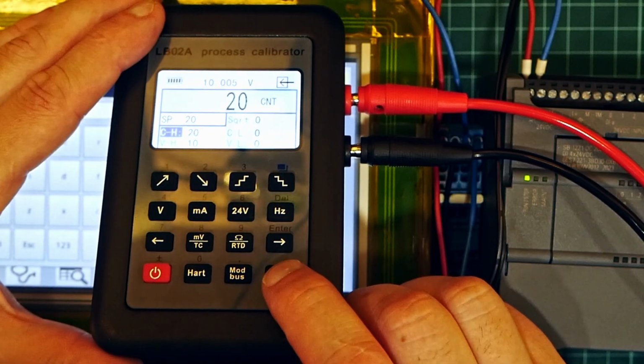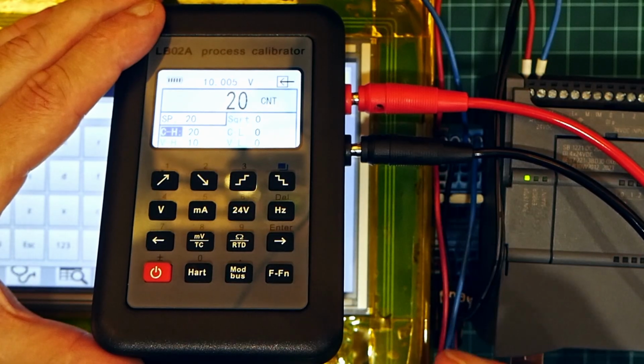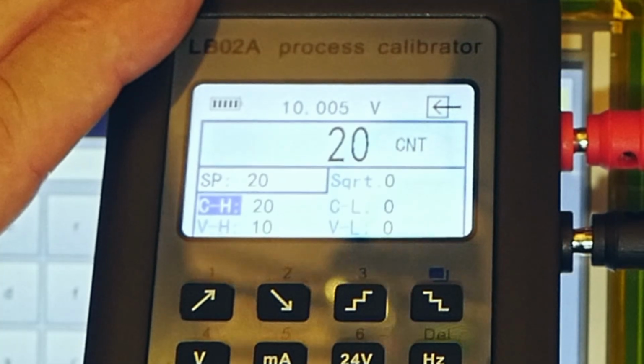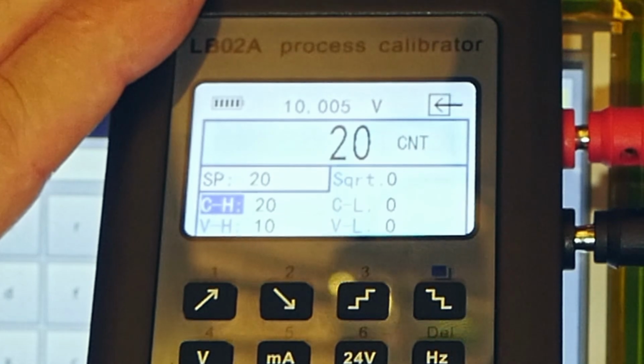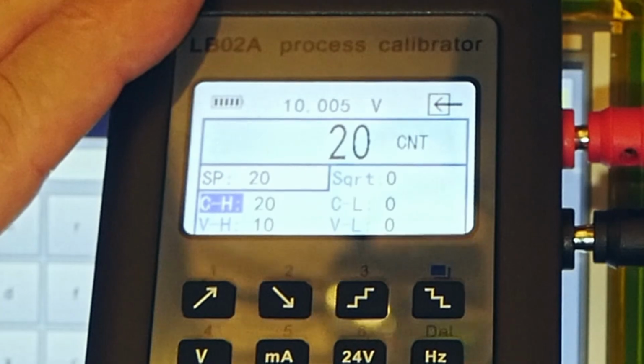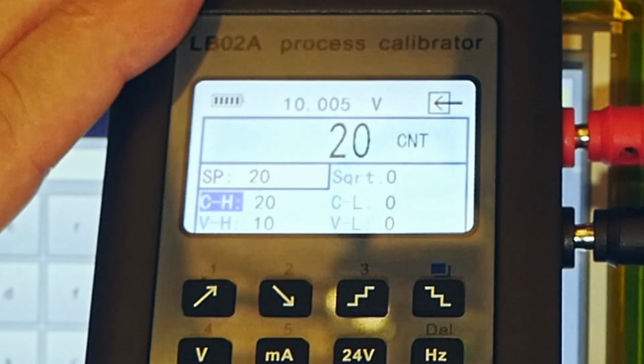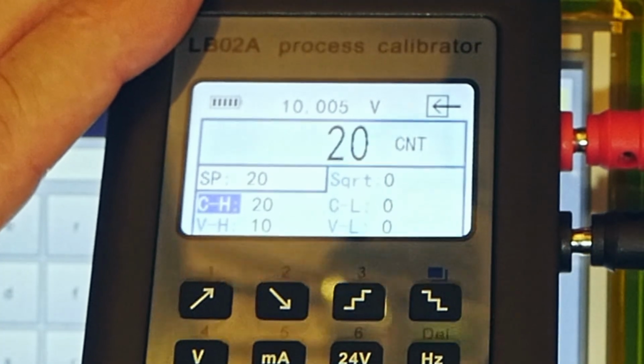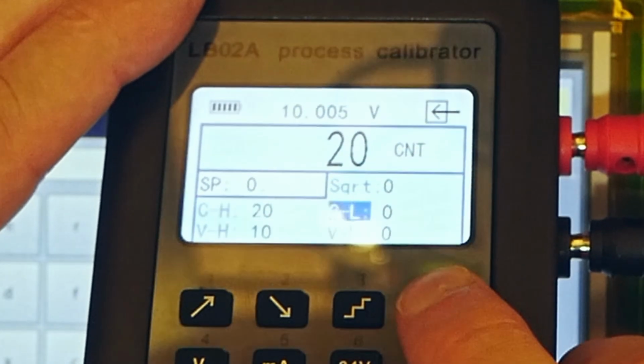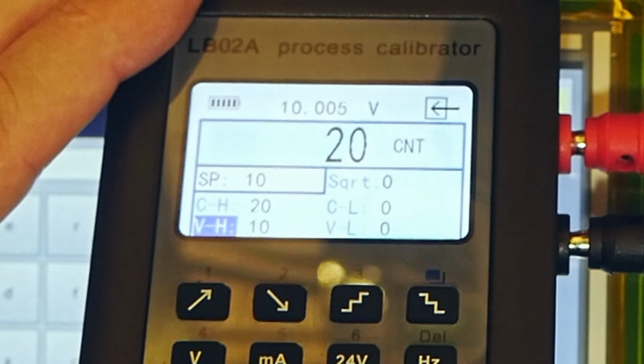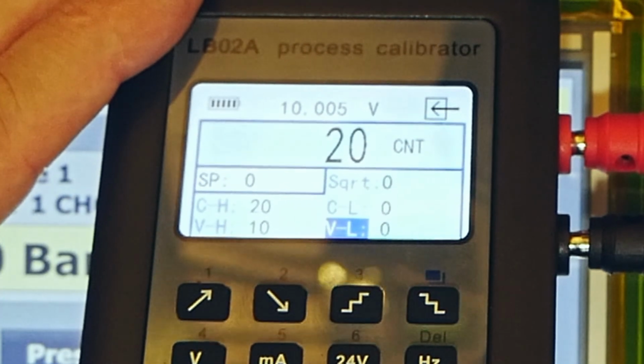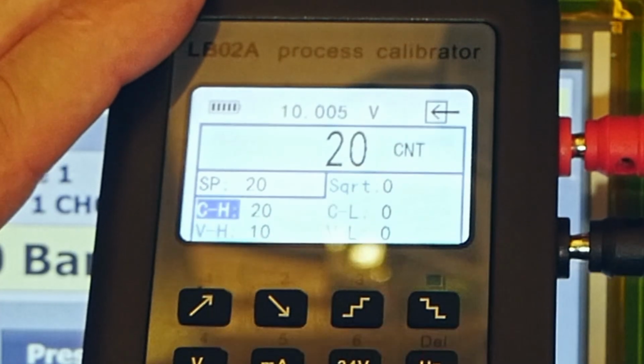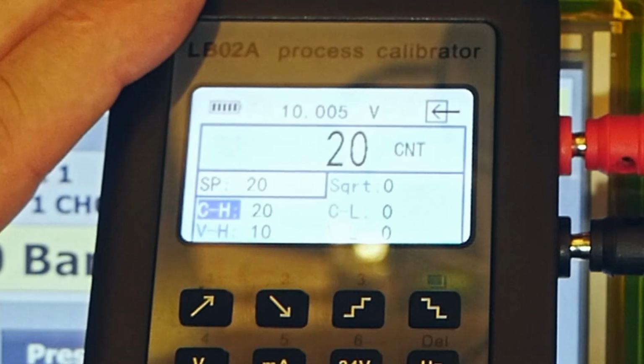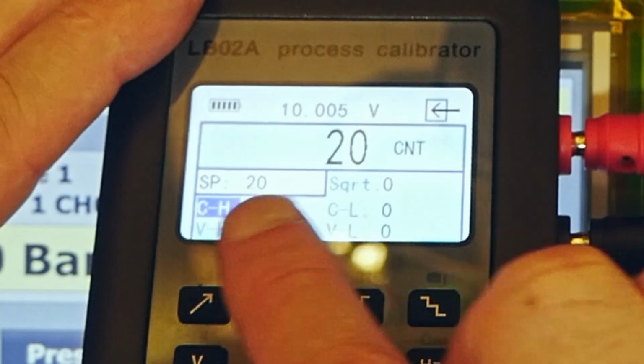So if we press the function button, we go to this kind of scaling menu, and let's say we have in our factory some sort of pressure sensor that sends a signal. When pressure is 0, it sends a 0 volt signal. When pressure is 20, it sends a 10 volt signal. I'm simulating this sensor with my bench power supply, but here we can actually write this scaling. So we can change the voltage high limit, I change it to 10, and we can change the voltage low, I change that to 0, and we can change the scaling, so I change the count high to 20. So you can change scaling here.